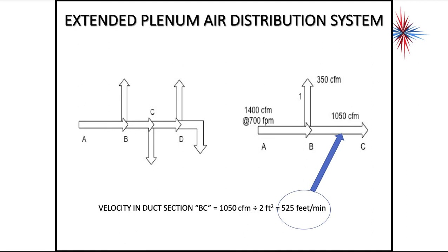Velocity in the duct section B to C, here is 1,050 CFM divided by 2 square feet. So we know our velocity here is 525 feet per minute, because we've lost the 350 here. We're still talking about the same one we had previously.